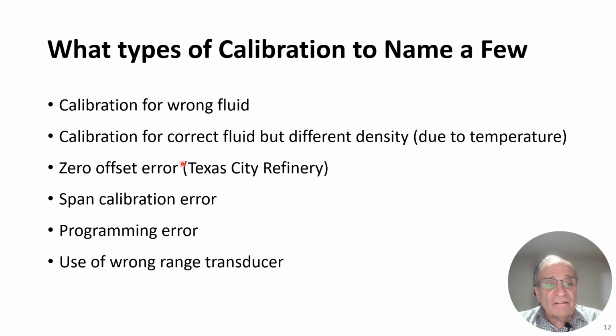Zero offset error is a very serious error because, not only did that happen in the Texas City refinery, but it gives you a false sense of security, especially if your liquid is over the top level. So if, as in the Texas City refinery, it's reading 5 foot level and it's really 6 foot level or 26 foot level, you wouldn't really know the difference.